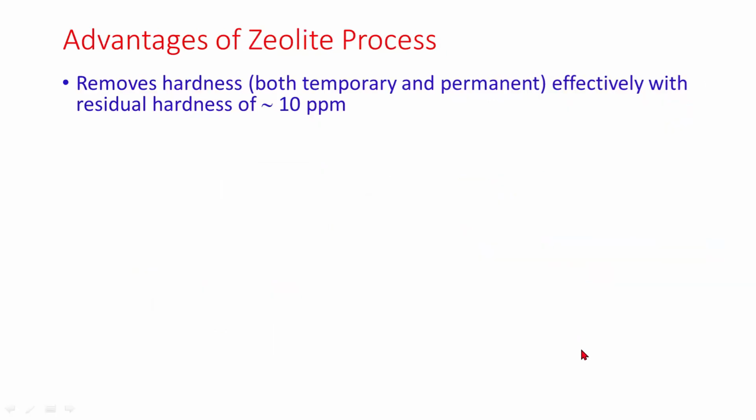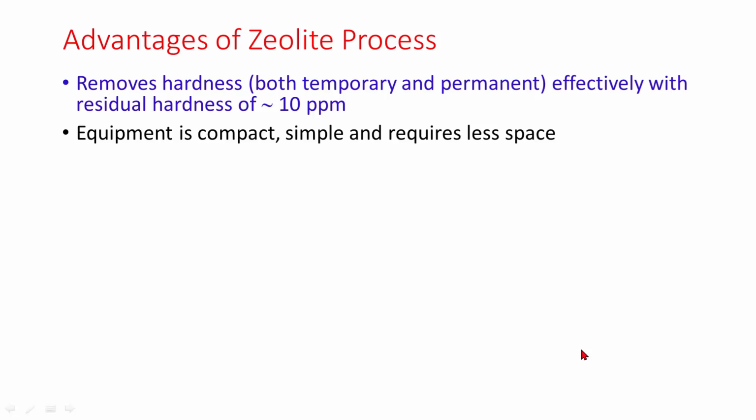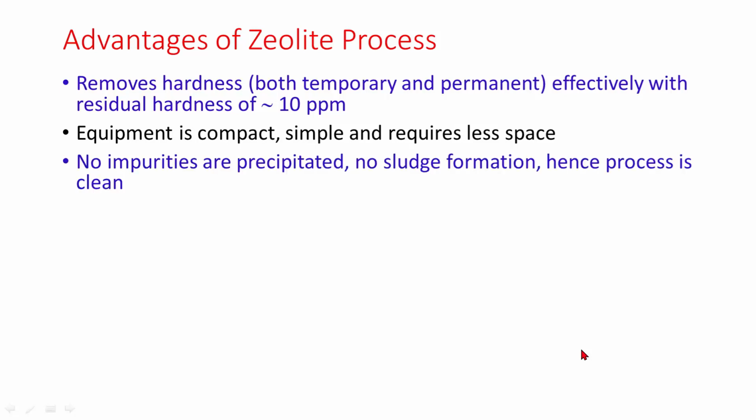Advantages of zeolite process: it removes hardness, both temporary and permanent, effectively with a residual hardness of 10 ppm. Equipment is compact, simple, and requires less space. No impurities are precipitated, no sludge formation as we see in case of lime soda process. Hence, this process is clean.